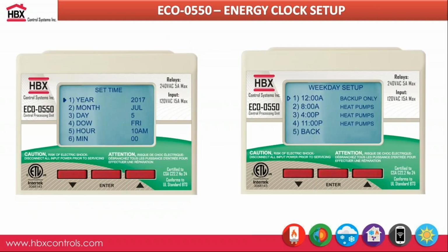In terms of energy clock, what really made this feature happen on the Eco 550 is that especially in Eastern Canada, in Ontario, like the Greater Toronto area, they had a really big spike in utility costs. So you can actually navigate when you want your backup boiler and heat pumps to run based off of time. It's like your thermostat programming options in terms of your setbacks. So you could say from 12 a.m. to 8 a.m. I just want my backup boiler to be running, and then from 8 to 7, it'll run my heat pumps with my backup boiler. So it's just options to save on utility costs using the energy clock setup with the Eco 550.